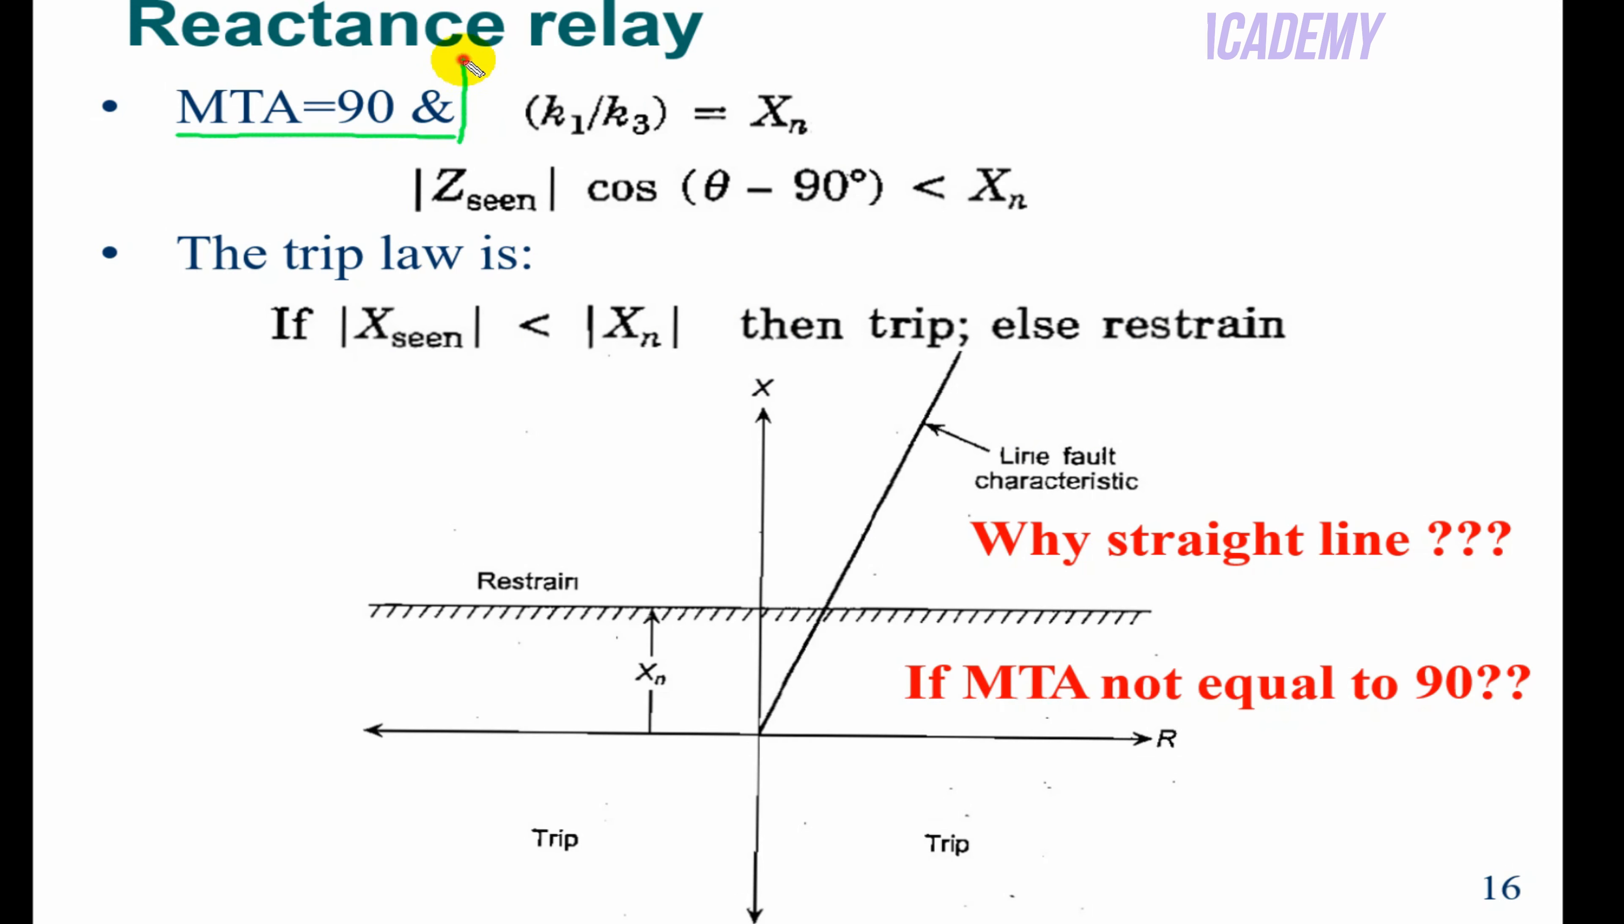What I will do is set MTA to 90 degrees. If I keep MTA at 90, Z_seen will convert to just reactance. Because if I have the Z line and I set MTA at 90 degrees, this becomes just X. This is what we call the reactance relay. Similarly, k1/k3 I set as X_n, which is the set value.